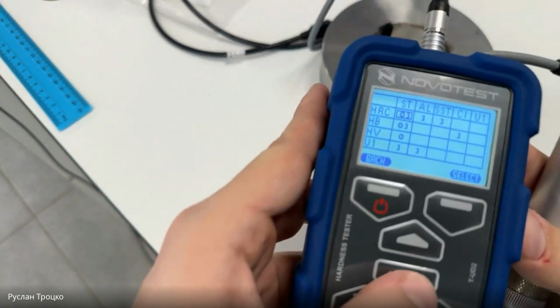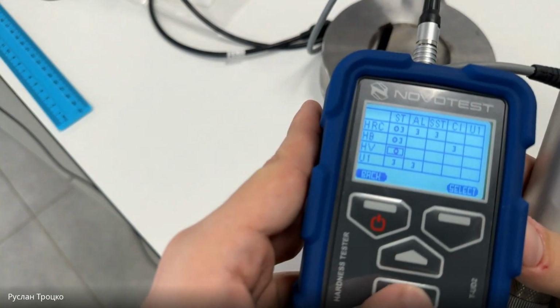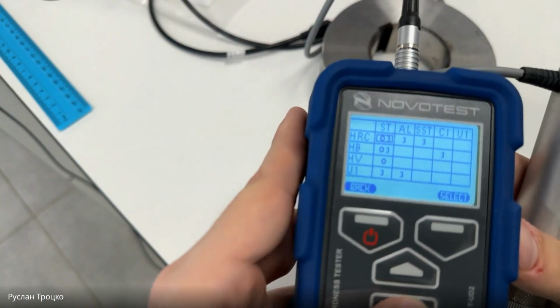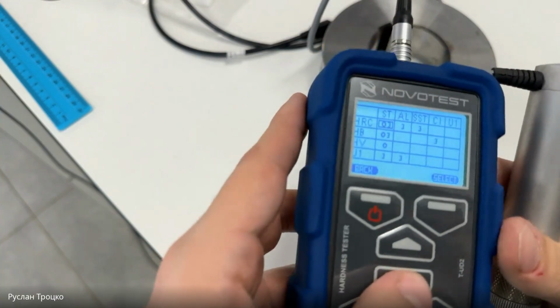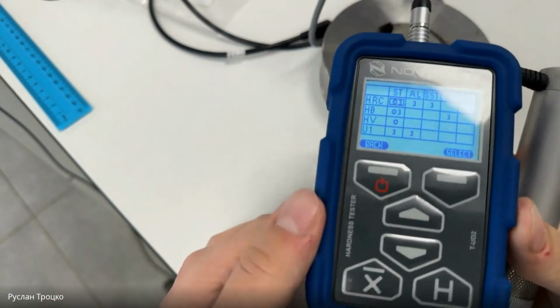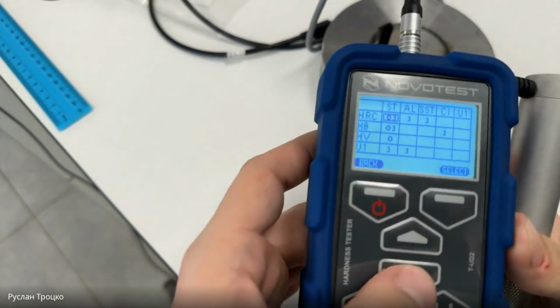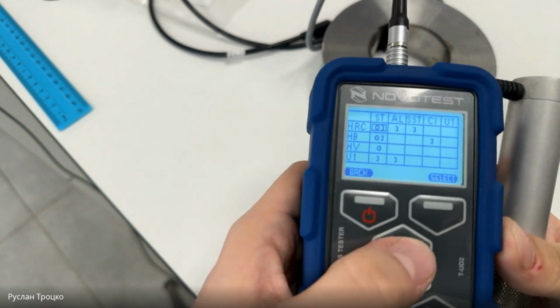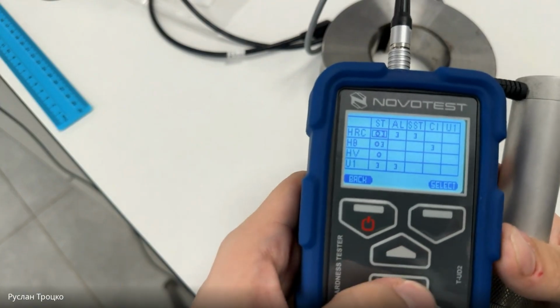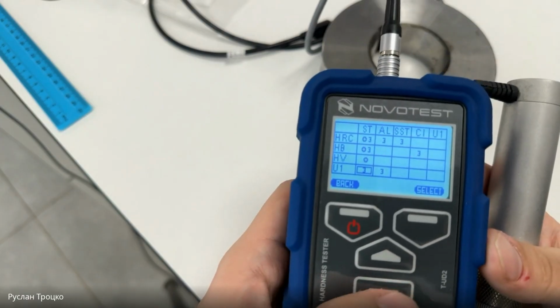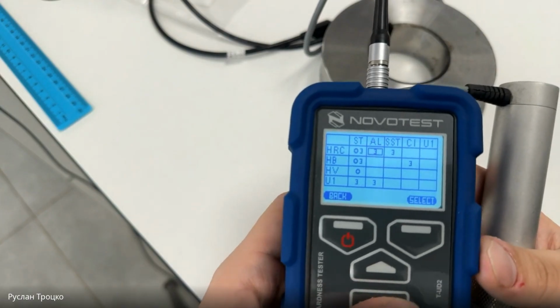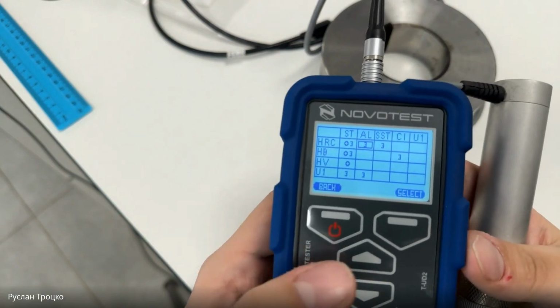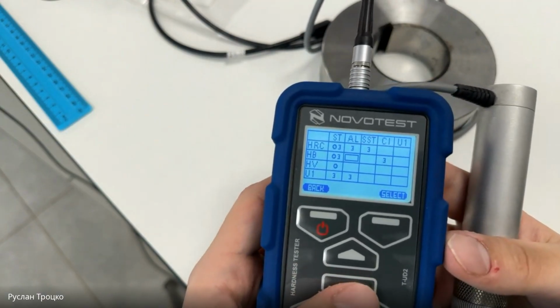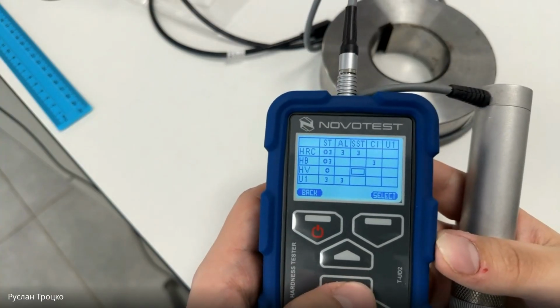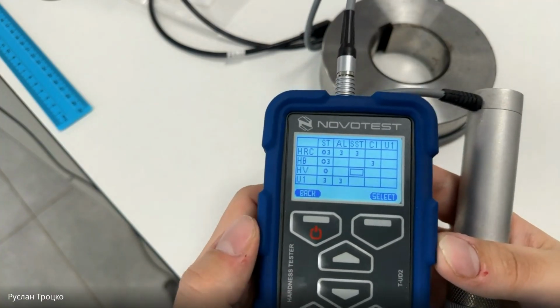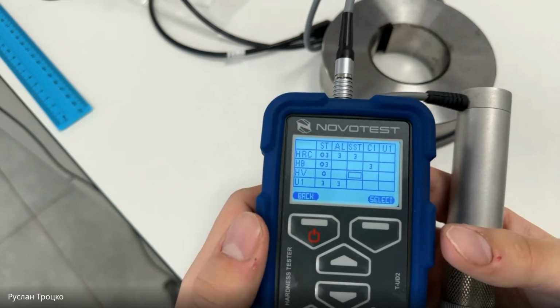Okay. You see, I have a plus icon here, plus 3. It's better, only plus. Plus means it's a factory calibration. In our device, in our cell phone, it was indicated as a blue cell. But here it is like this. So these are factory calibrations: this, this, and also this. If you have only a number, 3 means 3 calibration samples. It means it's your own unique calibration. If you have an empty cell, like this one, there is no calibration for this material and for this steel, for this scale.